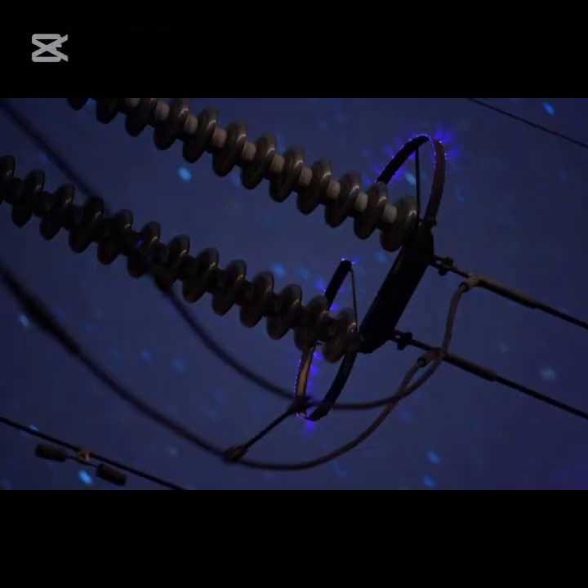Now that we've covered the basics of corona discharge, let's break down some key terminology related to this electrical phenomenon. 1. Critical disruptive voltage. Critical disruptive voltage is the minimum voltage at which corona discharge occurs. It is the voltage at which the electric field strength is sufficient to ionize the air or gas surrounding the conductor, resulting in a corona discharge. Below this voltage, corona discharge does not occur.